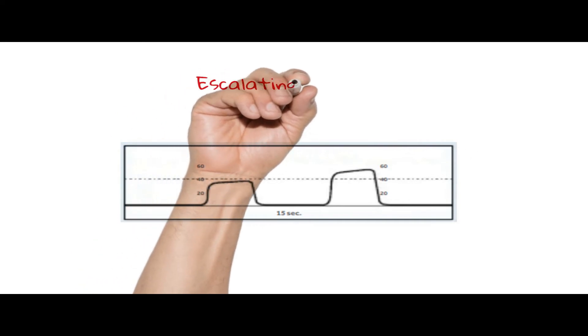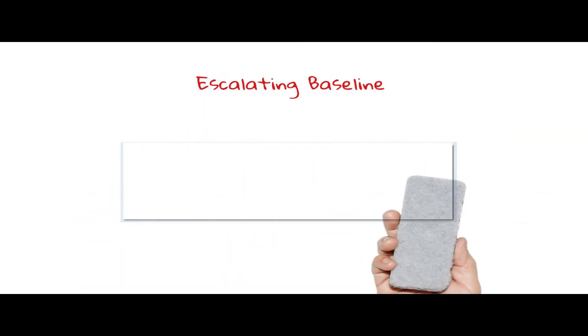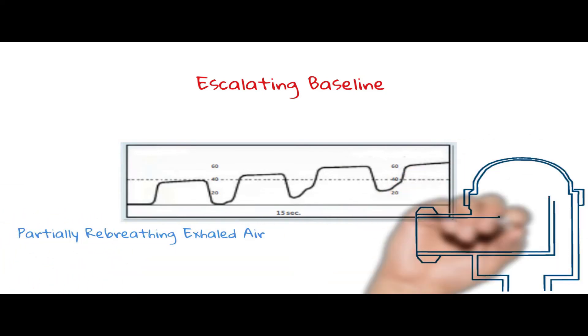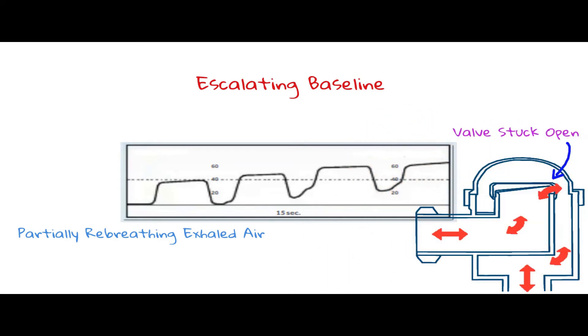Escalating baseline. An escalating baseline is occasionally seen in mechanically ventilated patients. This usually results from partially rebreathing exhaled air and it usually indicates an incompetent inspiratory or expiratory valve. It may also be the result of insufficient expiratory time or insufficient inspiratory flow.